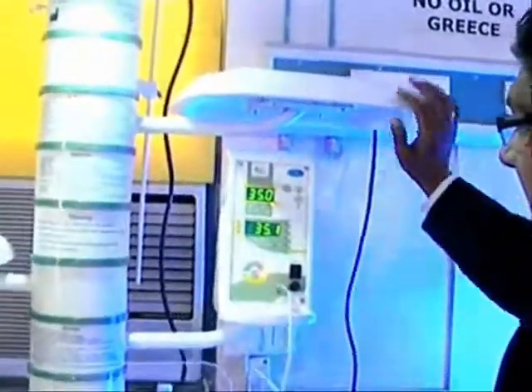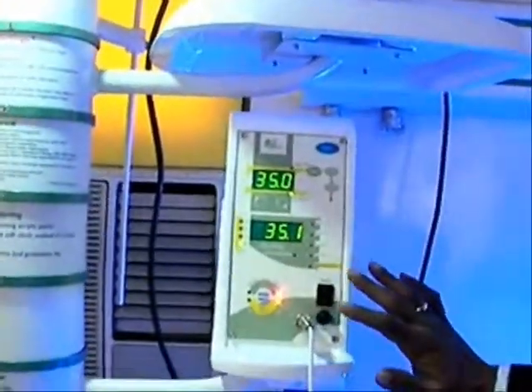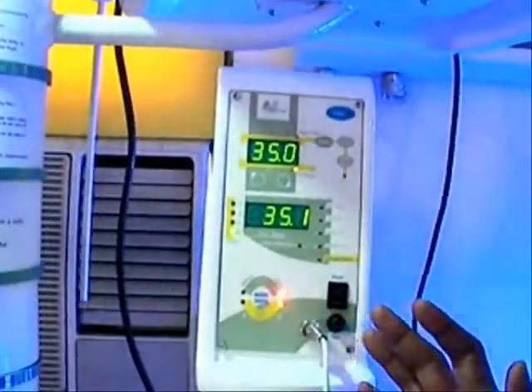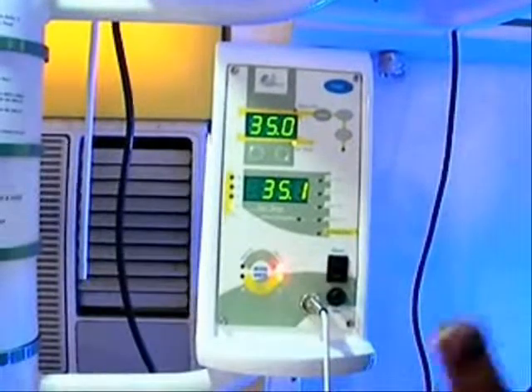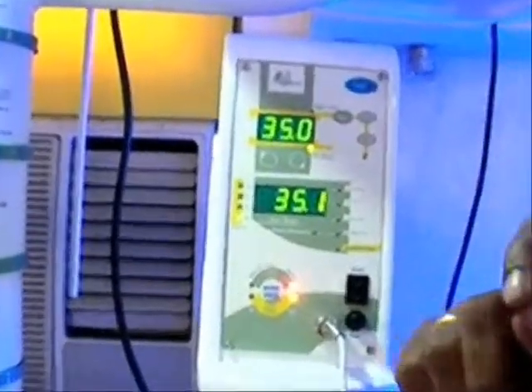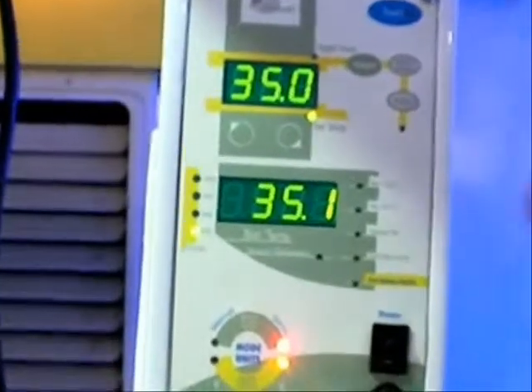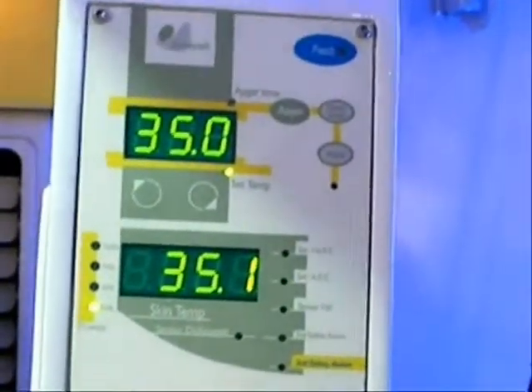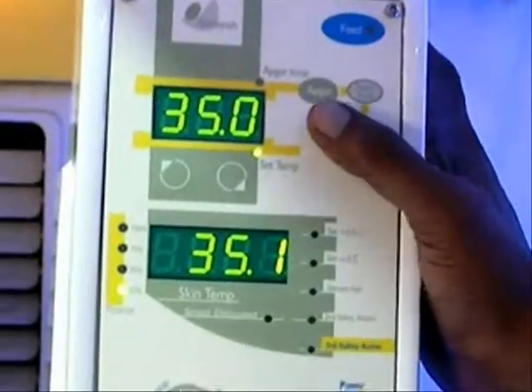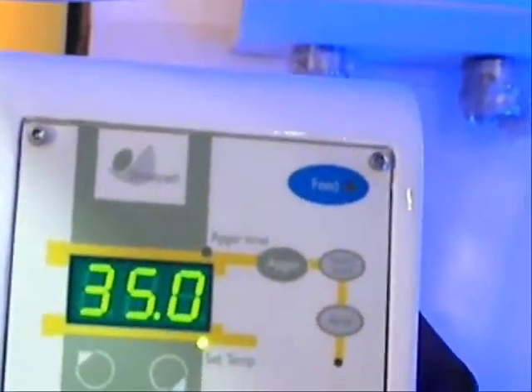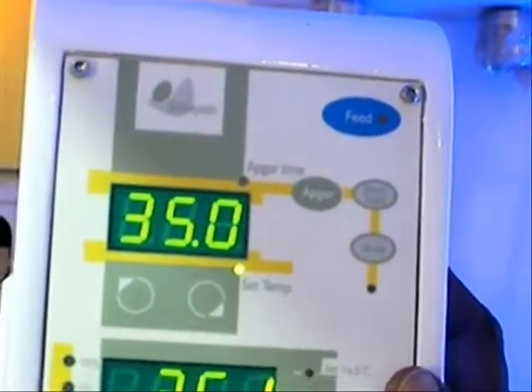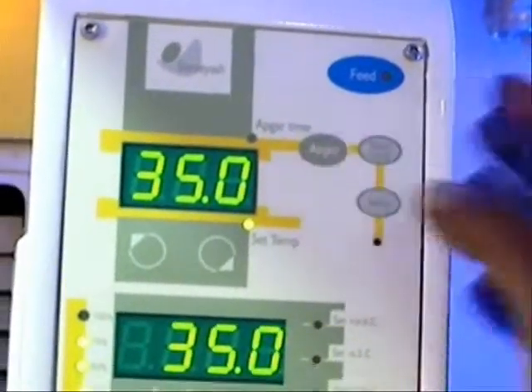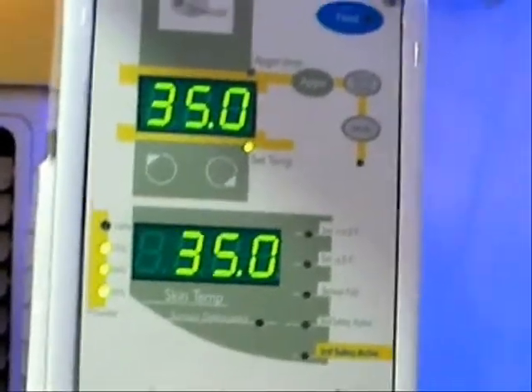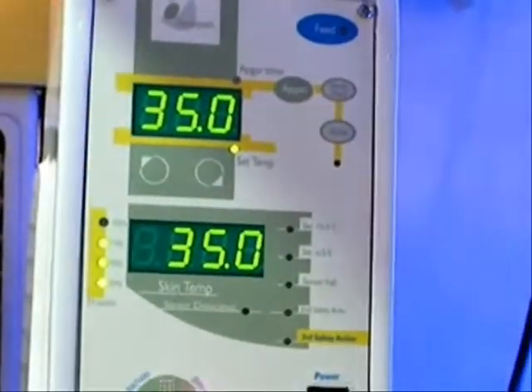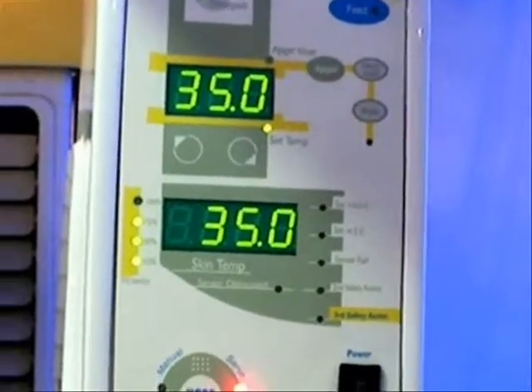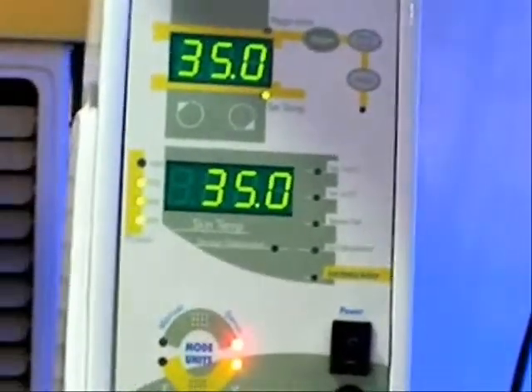Secondly, if you look at the temperature control mechanism, it's so beautifully designed. You have a lot of things incorporated in this, like a feed alarm. After each 2 hours, an alarm is automatically generated to warn the nursing staff regarding the feed schedule of the baby. It's a minor thing, but my friend, it makes a lot of difference. Plus, you have an APGAR timer. When this open care system is placed in a delivery room, immediately after the birth of the baby, once you press the APGAR time score, it gives you an alarm after 1, 3, 5, 7 and 10 minutes, so that the clinician can perform all the required things in the stipulated period.